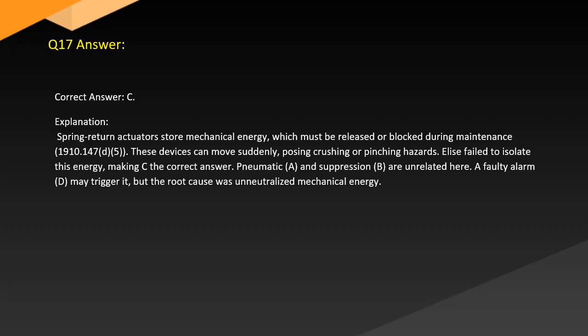Answer. Correct answer: C. Explanation: Spring return actuators store mechanical energy which must be released or blocked during maintenance. 1910.147 D5. These devices can move suddenly, posing crushing or pinching hazards. Elise failed to isolate this energy, making C the correct answer. Pneumatic and suppression, B, are unrelated here. A faulty alarm, D, may trigger it, but the root cause was unneutralized mechanical energy.